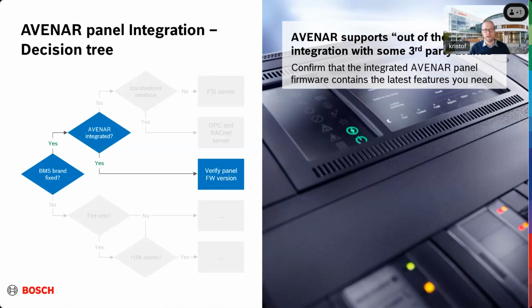We had now FSI, we had OPC, we had BACnet. What if AVENAR is already integrated making use of one of these three servers? Then we always recommend you to verify the panel firmware version. You never know that the supplier of this building management system used an old firmware version, and this old firmware version is not providing a feature that you need. Let's say the latest interface module or the latest sounders.